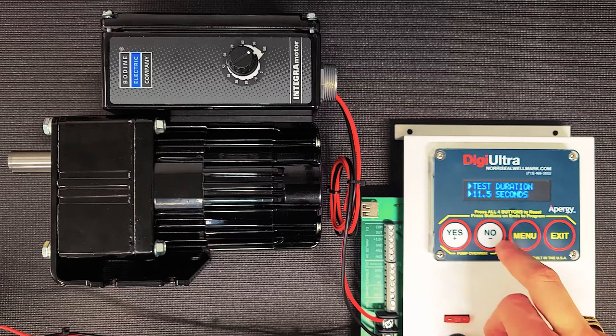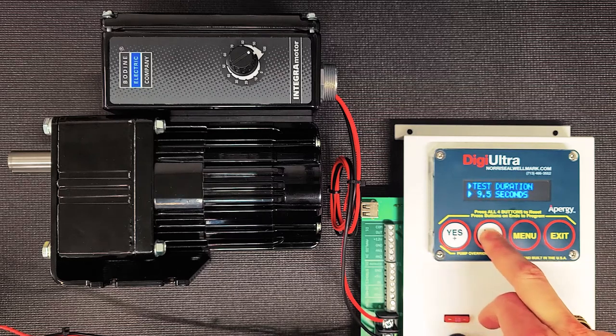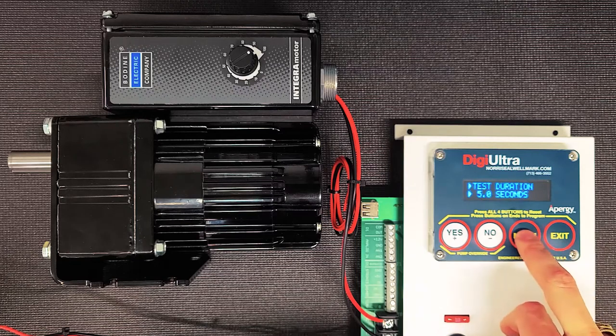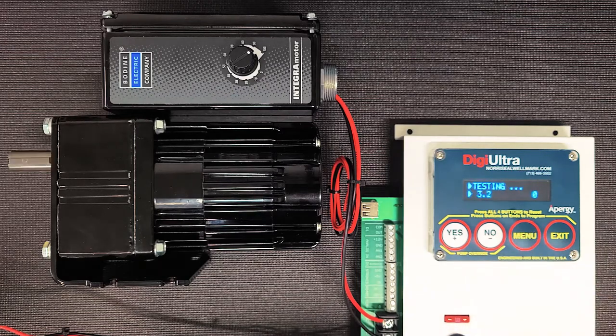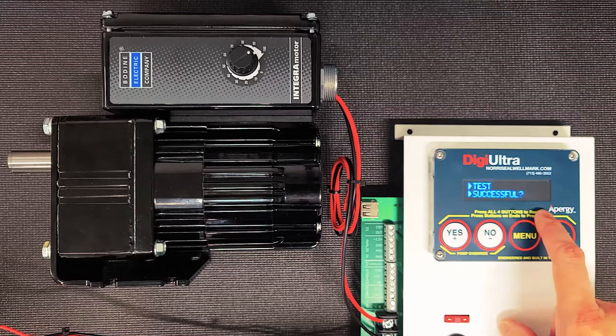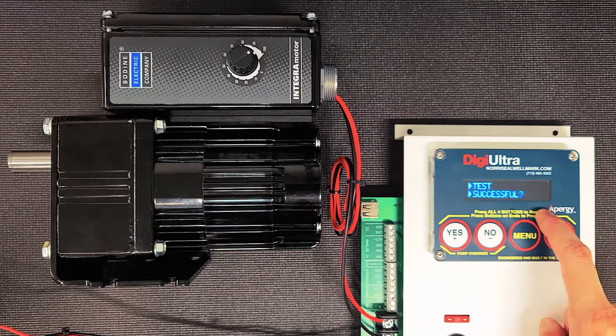So what we'll do here is set the test duration to 5 seconds just for the sake of this video. And when you press menu, the test will begin. What this is going to do is just run the motor for the 5 seconds. Assuming you have your rate gauges isolated, you'll notice that it's pumping down. On the right side of that screen previously, you'd notice that there's a counter. And if you're using the stroke input counter function on the controller, you will see that number increasing with the revolutions of the motor or the flow meter or whatever you're using to read pulses.